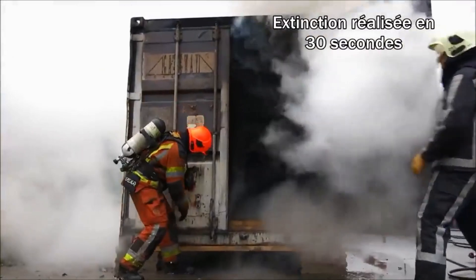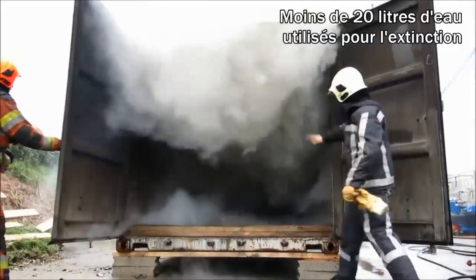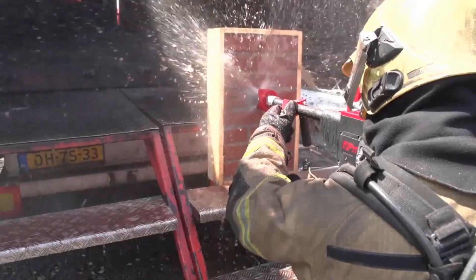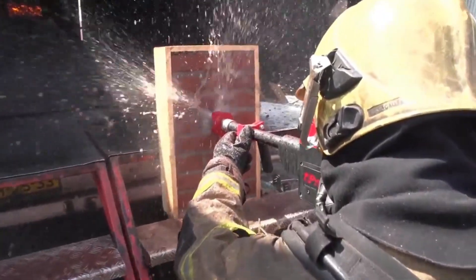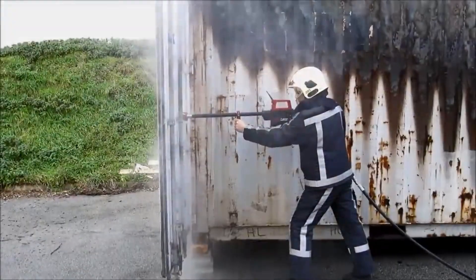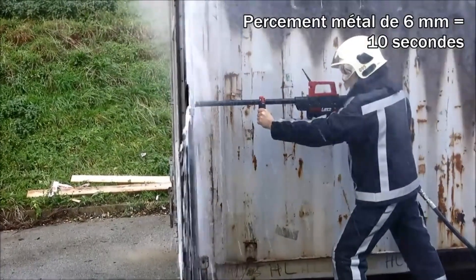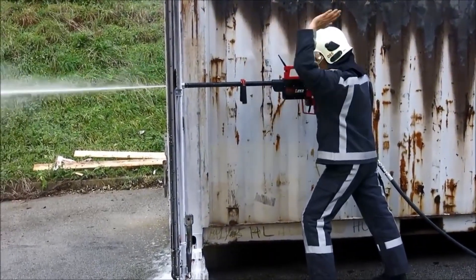Pyrolence also refers to high-pressure firefighting systems that allow the operator to attack fires from a safe distance, available in different models for industrial fires, structural fires, and vehicle fires. A specialized fire hose combines ultra-high-pressure water, fog, and garnet (an abrasive mineral) to cut through walls and structures, allowing firefighters to create access and cool hot gases before entering a building. The Pyrolence Cutting Extinguisher is a single handheld device combining abrasive water jet cutting with water spray extinguishing, rapidly cutting through burning materials while extinguishing flames simultaneously.